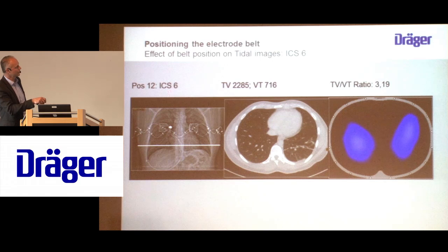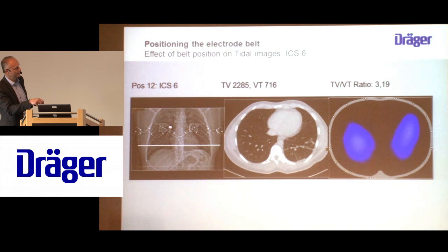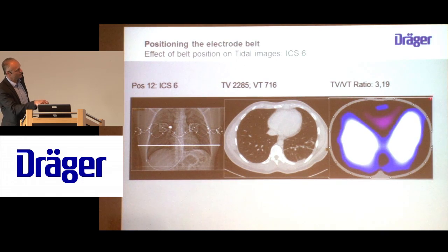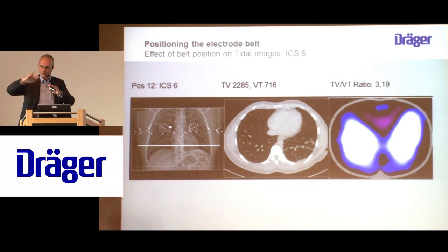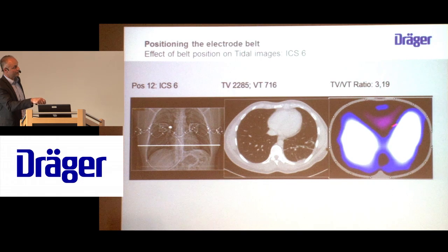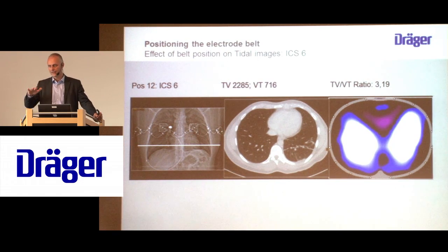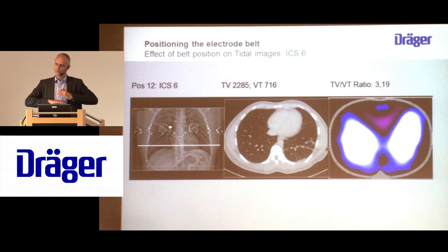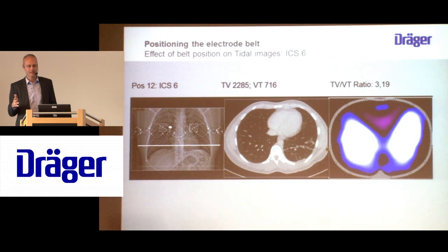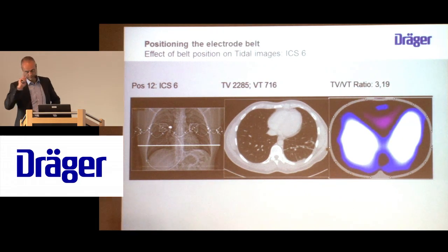At intercostal space 6, you can already see the ratio between the tidal volume and the tidal variation going down, because this mediastinal area is getting even larger. When there is less ventilation and these purple spots show a kind of phase opposition, which is subtracted from the ventilation signal, this ratio decreases. This is especially relevant if you intend to make PEEP changes: if you attached the belt at a high PEEP level and then reduce PEEP, the diaphragm distance to the belt changes. If you're too low, this can be misleading — something even some EIT researchers have not been aware of.